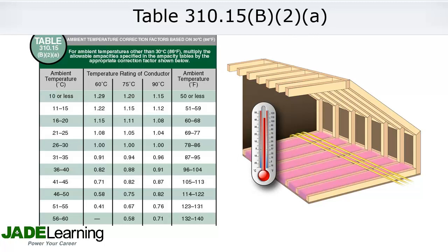The current carrying capacity must be reduced by applying the correction factors in table 310.15(B)(2)(A). In this case, the NM cable could carry only 87% or 0.87 of the value from table 310.15(B)(16) based on using the 90 degrees C column of table 310.15(B)(2)(A) for ampacity adjustment.